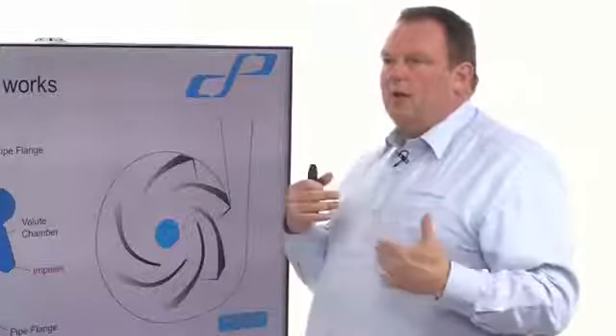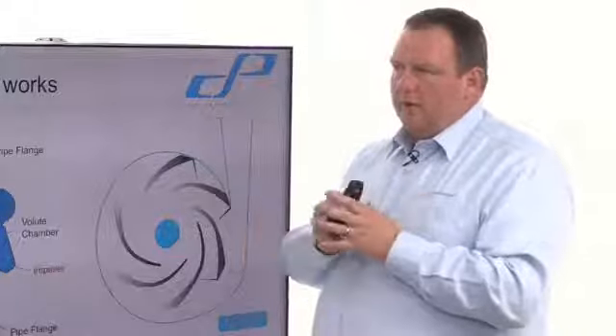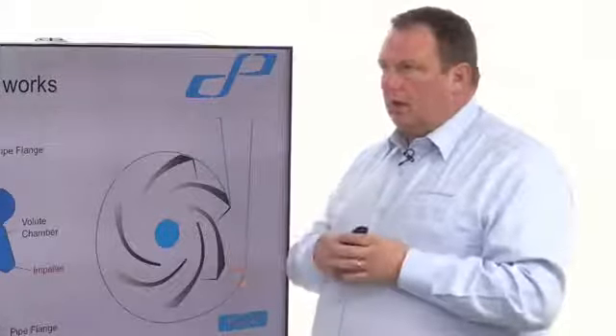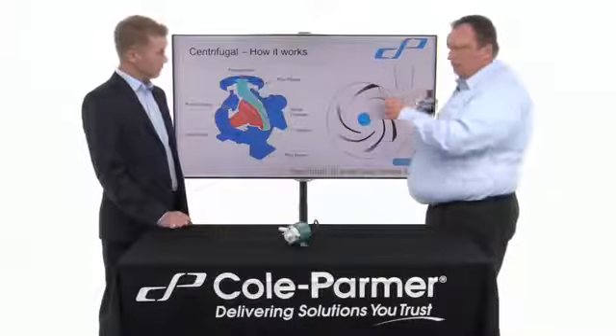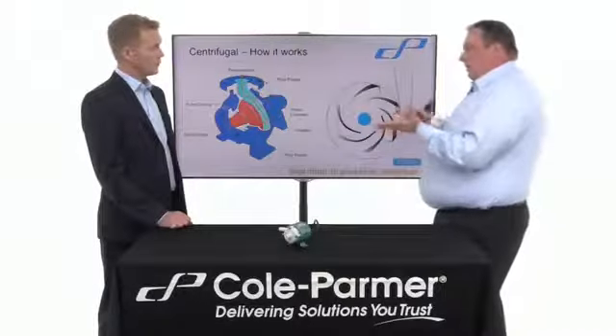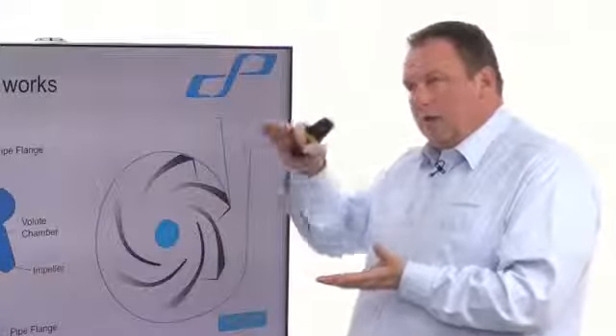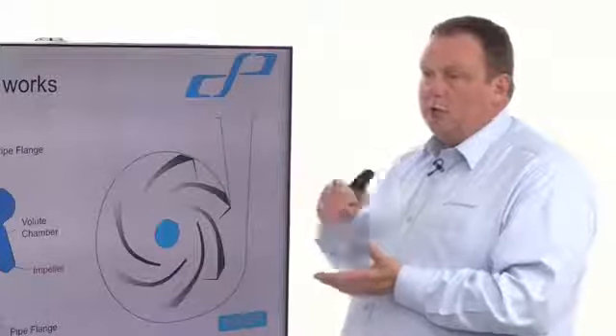They are the most engineered, worked-on pump. They do achieve very high flow rates. They can achieve high pressures. I think the highest one I've ever heard of is about 480, 500 bar. That's not within our range, but that's used within the petrochemical industry. Right. So you have to put pump on pump on pump, but you do it all on the same shaft, and then you can drive all the heads and flow them into each other, and you can increase pressure.